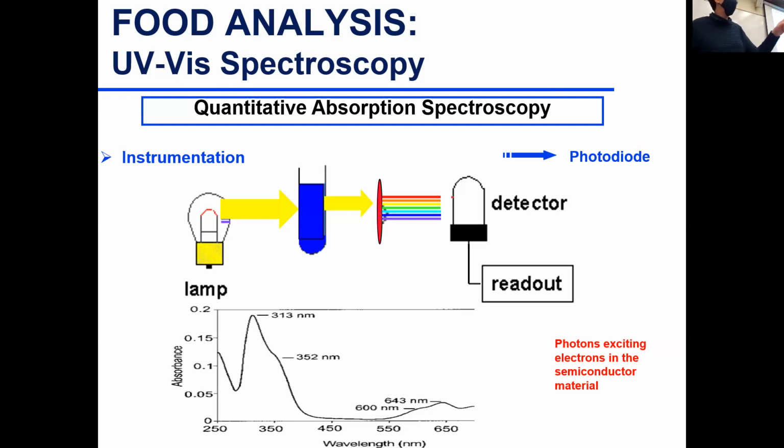Any questions on that? Yes, there. So one thing is the regular UV detector is much cheaper than this one, and you cannot produce a scan. You can only use it as one, or some UV detectors allow you to scan at 2 wavelengths.